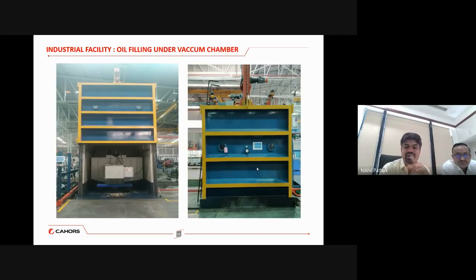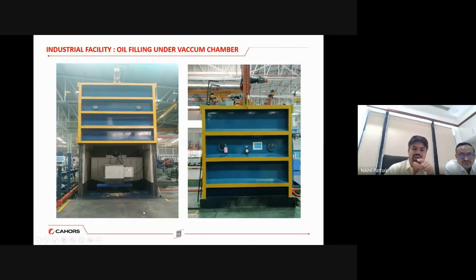And then once the oil filtration is done, in parallel, as I explained, the transformer is kept inside the vacuum chamber, and then the shutter is closed. Then the oil filling starts with this oil filling gun. You can see these oil filling guns are inserted in the oil filling pocket, so that the operation is not manual. It is an automated control circuit, so that the oil filling happens, the oil filtration happens, and the filtered oil is filled in the transformer. Once the filling is over, the transformer is taken out and connected to the pressure test.